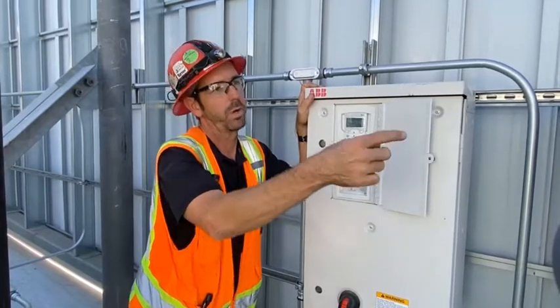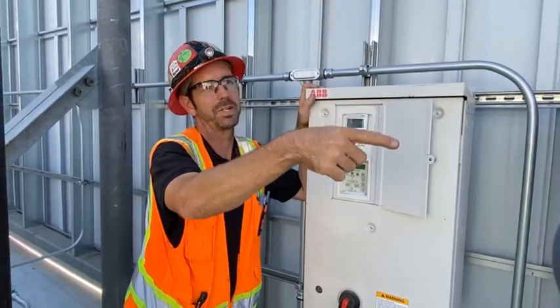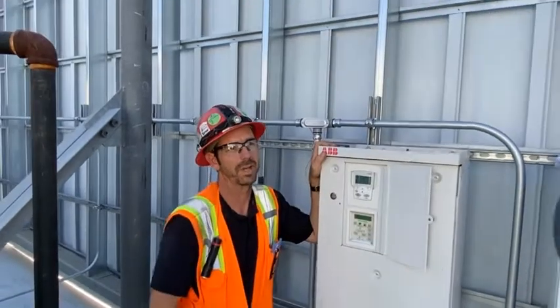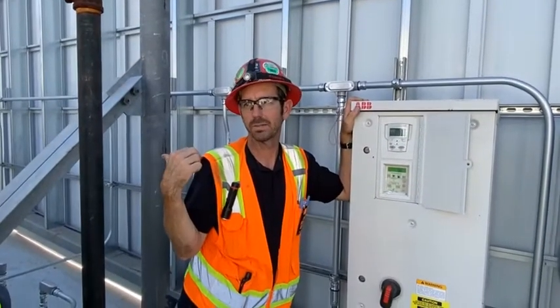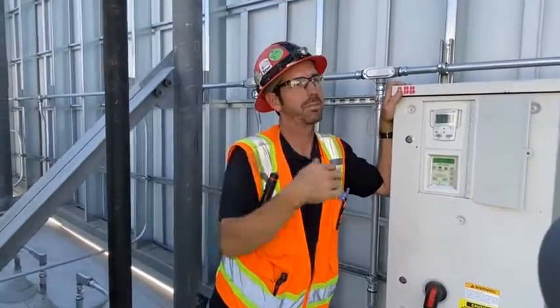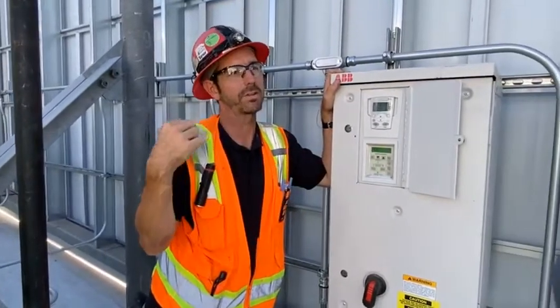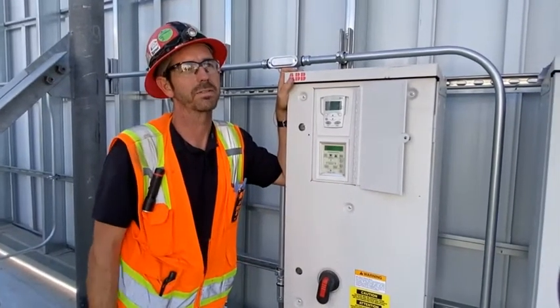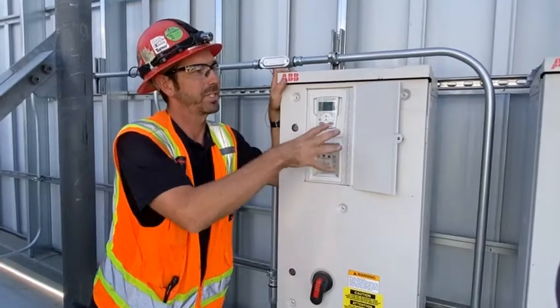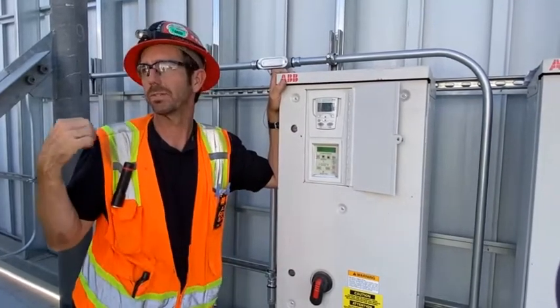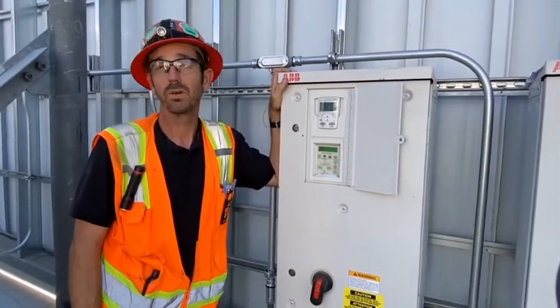Two VFDs, one per pump. A pump is redundant. We should only be running one pump at a time. Same with the heating hot water system. The drives are the same, exact same configuration. Those drives are actually just smaller than the chilled water pump drives. The programming, all the stuff I showed you on these two, is going to be exactly the same on those up there. Questions on the drives?